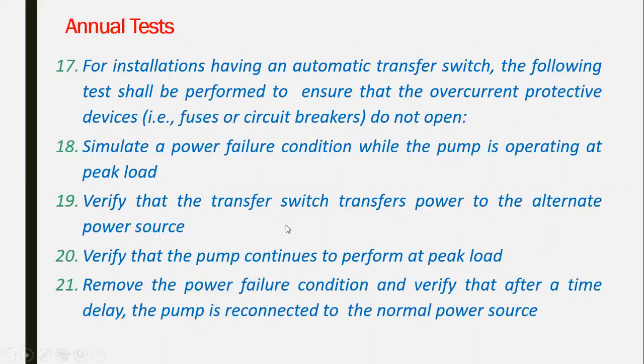Then return to the original situation by removing the power failure condition and verify that after a time delay, the pump is reconnected to the normal power supply. And you can see here, there is a time delay. After a time delay, once we remove the power failure, it is instantaneously connected to the emergency source if the main source of electricity is not coming from the transformer. And this is a trick here.